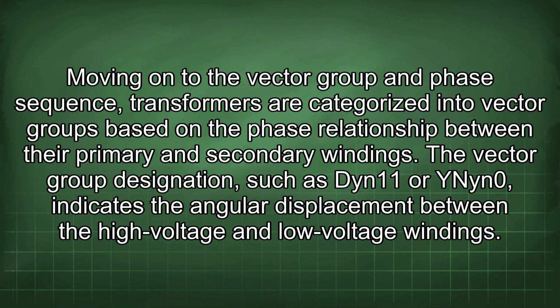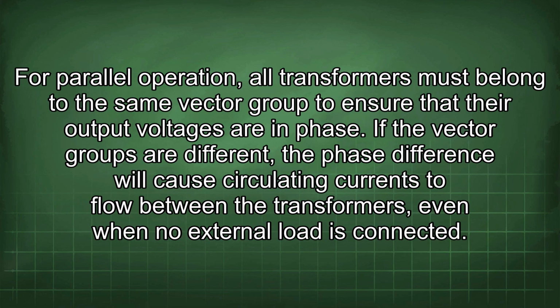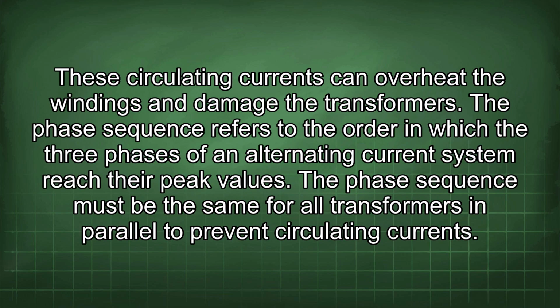The vector group designation, such as Dyn11 or YNyn0, indicates the angular displacement between the high voltage and low voltage windings. For parallel operation, all transformers must belong to the same vector group to ensure that their output voltages are in phase. If the vector groups are different, the phase difference will cause circulating currents to flow between the transformers, even when no external load is connected. These circulating currents can overheat the windings and damage the transformers.